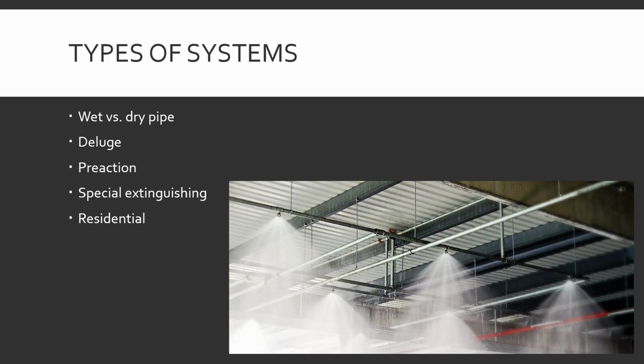Then real quick before we talk about this slide, fire department connections. There's usually a certain amount of PSI you want a truck with a pump to provide, just to help keep the system along. You don't want to put the sad little brush truck at 100 GPM connected up to it. You want a full engine, preferably a dedicated engine, so it's not trying to feed two or three attack lines and a sprinkler system. You want an engine for the sprinkler system if you're going to go that way, and then an attack engine or other engines.